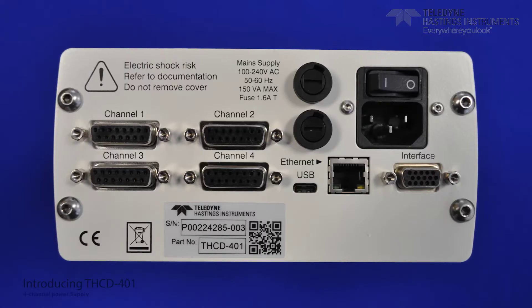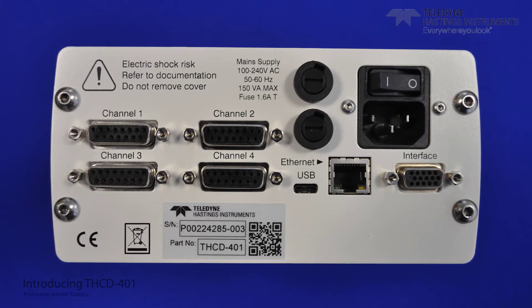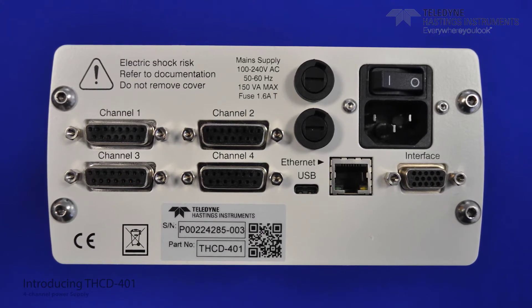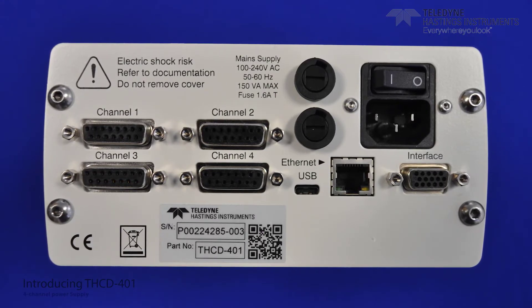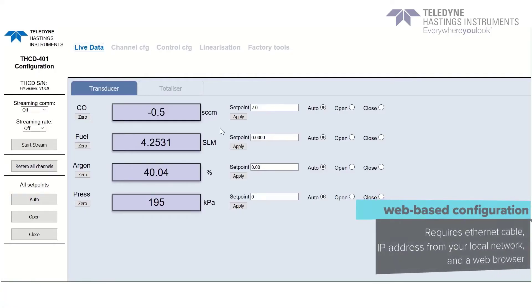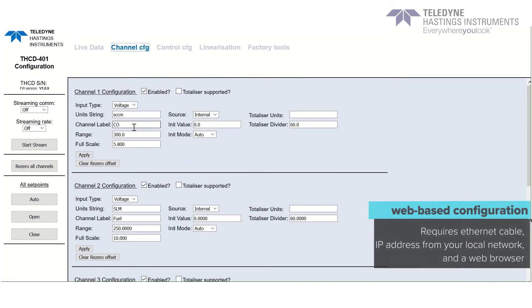The THCD-401 can then send a command signal back to the device to adjust or control the flow rate. To power your devices, you just need to connect them using the correct cable to the labeled channel ports on the rear panel. We have also included an interface port to send a voltage signal out to an external controller, as well as a USB-C and an Ethernet port for serial communication. The Ethernet port gives the device its own IP address, and once entered into any browser, you can view live data streams or access the customizable channel configuration.